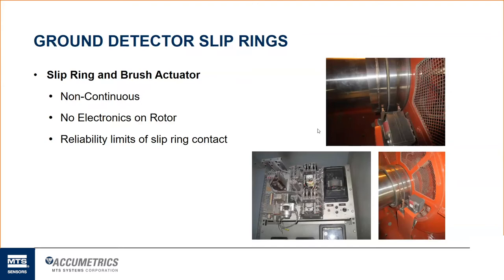They have these brushes that touch down, graphite brushes, I believe, that are powered by a solenoid. They touch down on the shaft as it's spinning, usually once per day. They inject a DC voltage that biases the negative side of the field slightly higher than rotor ground. Then it looks for current flow between the negative side of the field and rotor ground. If there is current flow, there is some circuitry that will detect if the resistance is below a certain threshold. Usually that's set at 10K ohms. Anything below 10K ohms will trigger an alarm and let the user know you've got a ground fault.